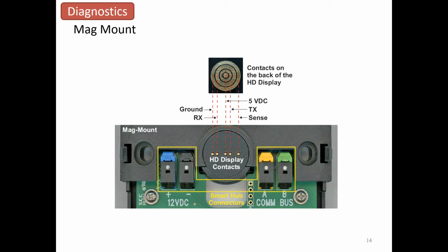Okay, so if you just put left and outside and inside, and then the two inside, they're not going to wire properly. So please pay attention to that. I think in the new version we're eliminating these mag mounts. What we're doing, you'll have a standard base that goes on the wall. It will have 4 wires with the little lug nuts for the small thermostat screwdrivers, and the display will snap in there. That's what's going to happen here fairly soon.